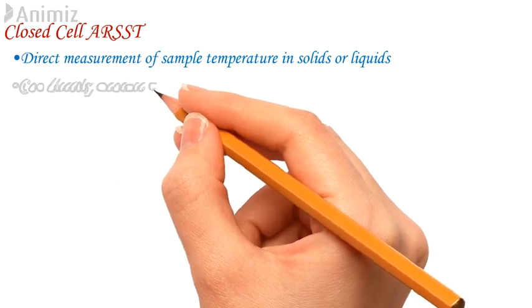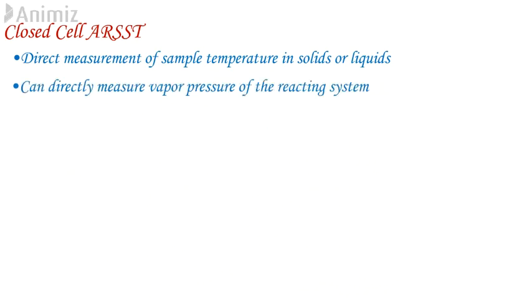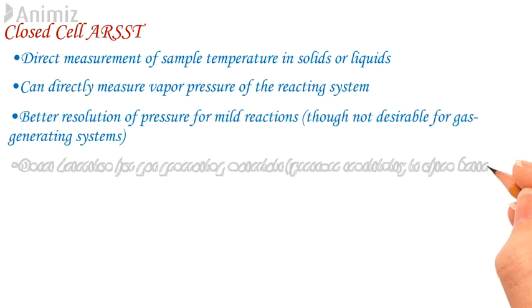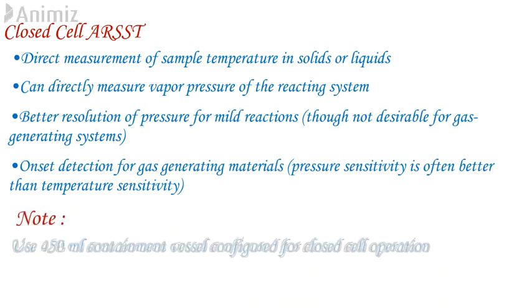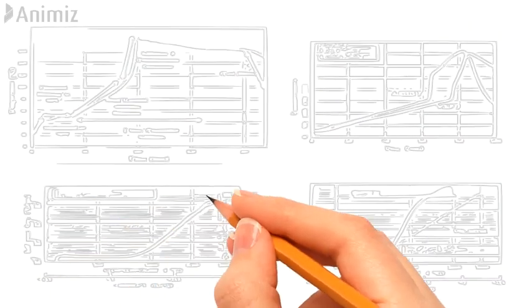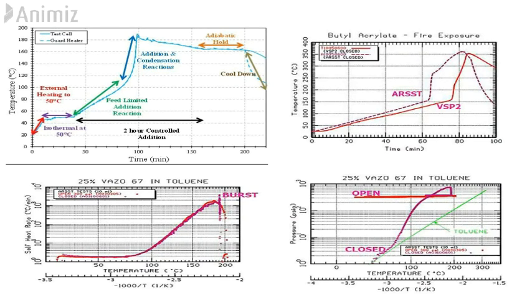Advantages of closed cell ARSST include: direct measurement of sample temperature in solid or liquid state, direct measurement of vapour pressure of the reacting system, better pressure resolution for mild reactions, and onset detection for gas-generating materials. It is recommended to use a 450 ml containment vessel configured for closed cell operation. ARSST is used to estimate process safety parameters including heat of reaction, heat of mixing, total adiabatic temperature rise, onset temperature, tempering temperature, self-accelerating decomposition temperature, and time to maximum rate.